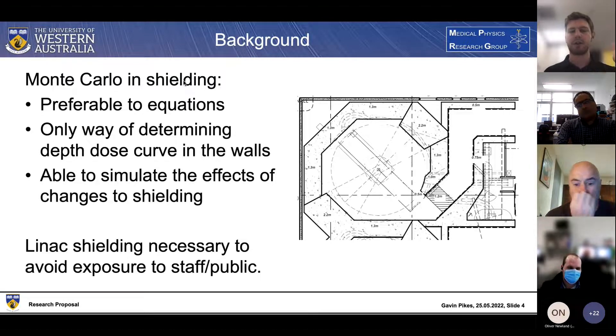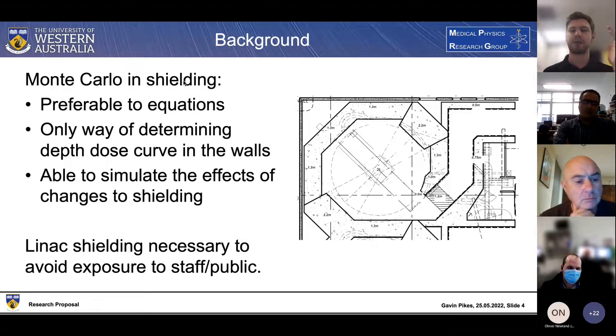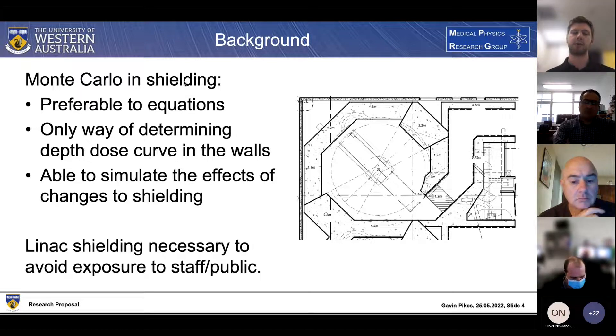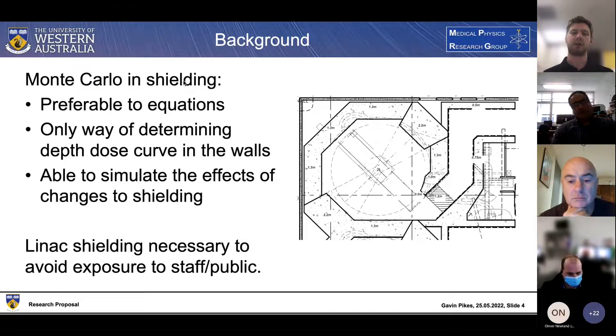Linac shielding is quite necessary to avoid exposure to staff and the public not receiving radiotherapy, as the radiation involved can be quite harmful to healthy tissue. We want to restrict all that exposure to within the bunker itself and avoid exposure to the rooms outside. Monte Carlo is quite relevant in quantifying where our radiation has been and where our energy has been deposited.